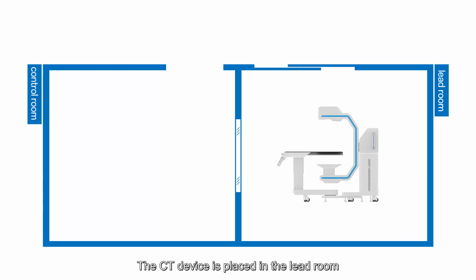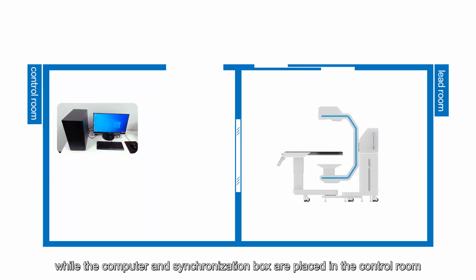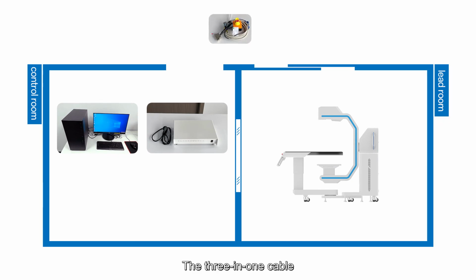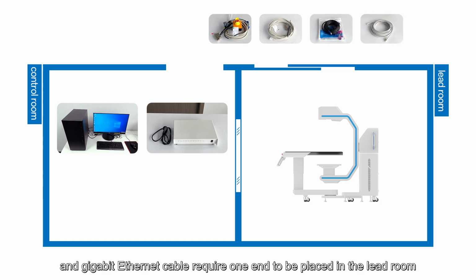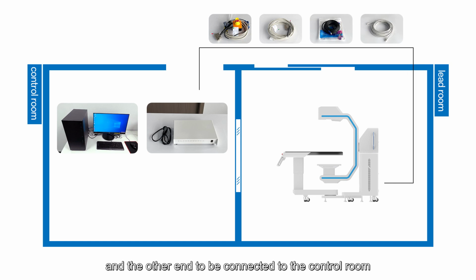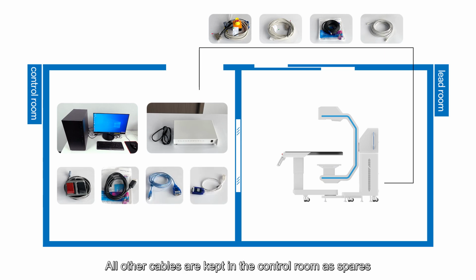The CT device is placed in the lead room, while the computer and synchronization box are placed in the control room. The 3-in-1 cable, tablet synchronization cable, 10-meter HDMI cable, and gigabit Ethernet cable require one end to be placed in the lead room and the other end to be connected to the control room. All other cables are kept in the control room as spares.